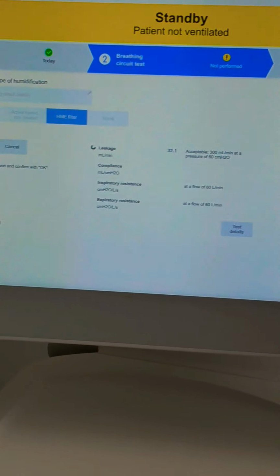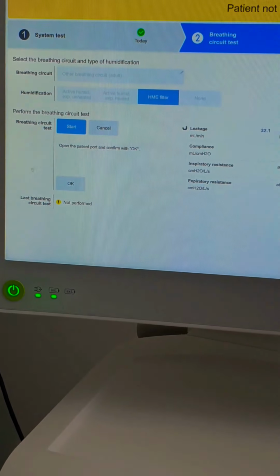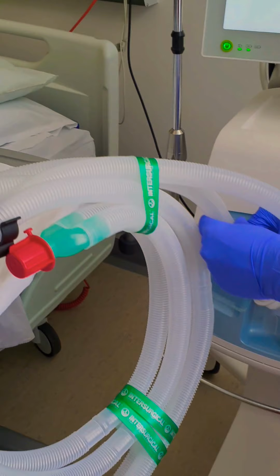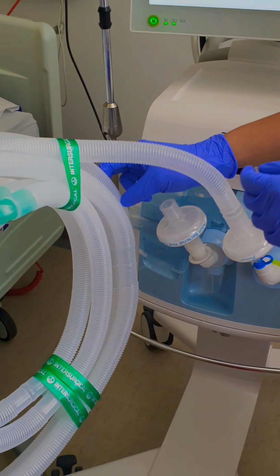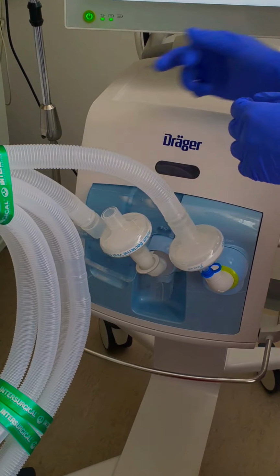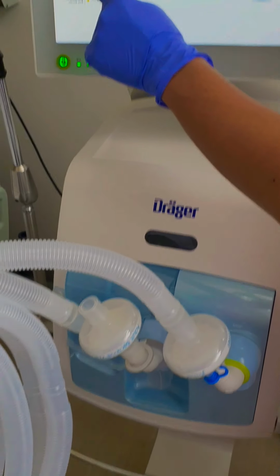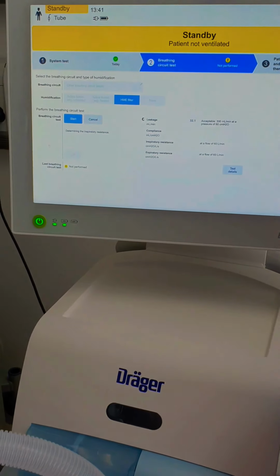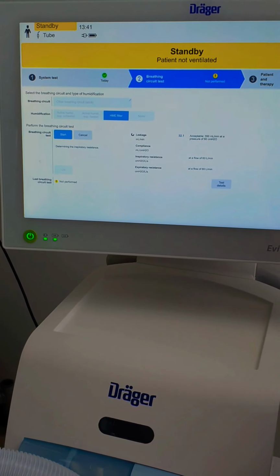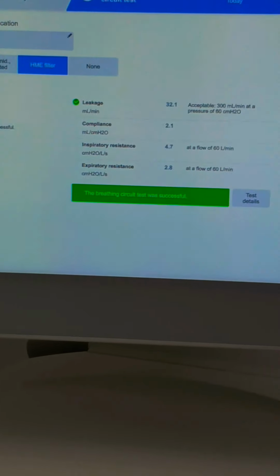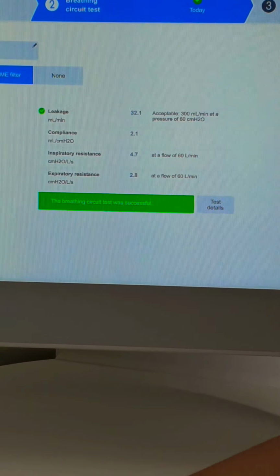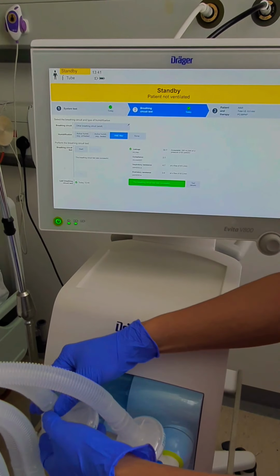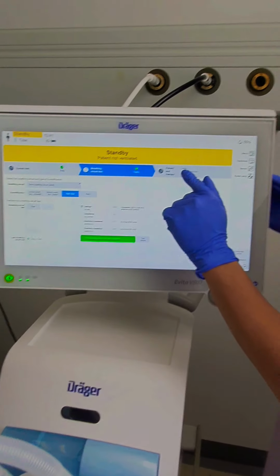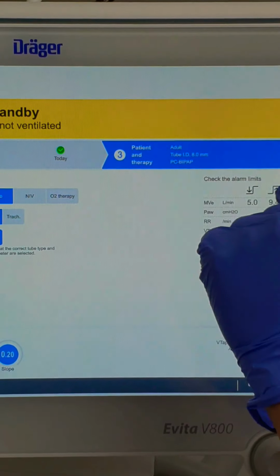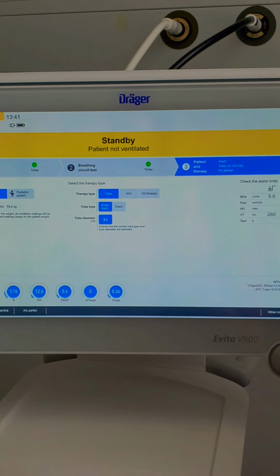It just says it's determining resistance. And now we have to open the patient port and confirm with OK. So it's basically just disconnecting the expiratory port from the tubing, and then we're going to press OK on the ventilator, and it's going to proceed testing. And now the breathing circuit test was successful. We're just going to put this circuit back on, and now we are going to proceed to the patient and therapy, where you can set up the mode of the ventilator you want.